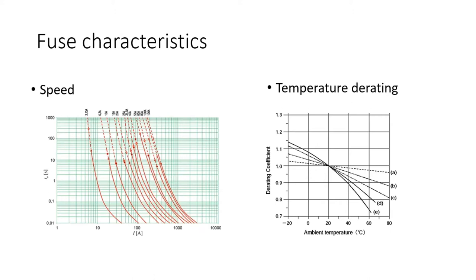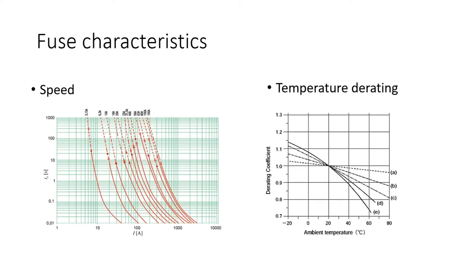It is very important to know how quickly the fuse reacts to different currents because some equipment can be more or less sensitive to the amount of time they can withstand short circuit current. Sensitive electronics equipment cannot stand more than a few milliseconds of short circuit current, while heating elements or electrical machines can withstand short circuit current a few times the nominal value for long periods without harm.